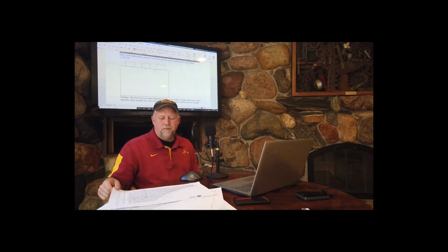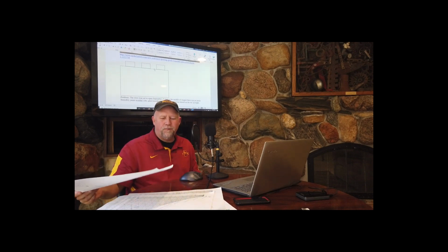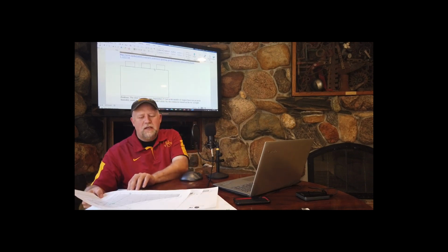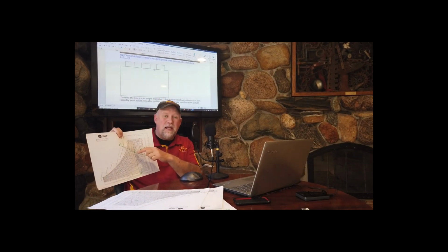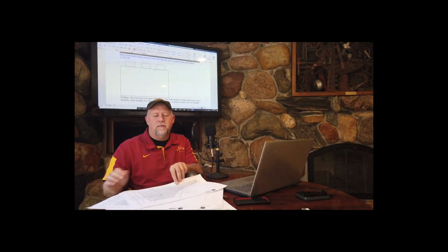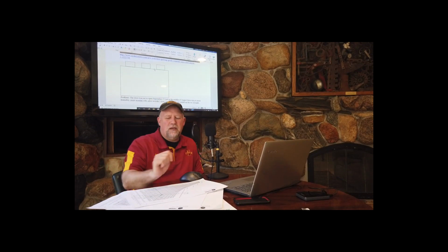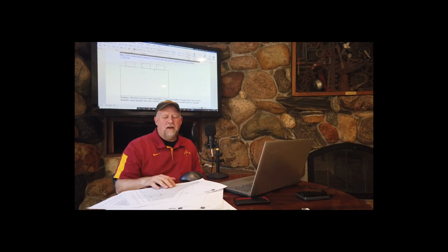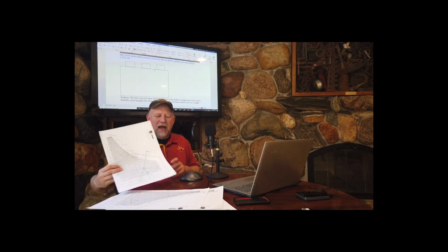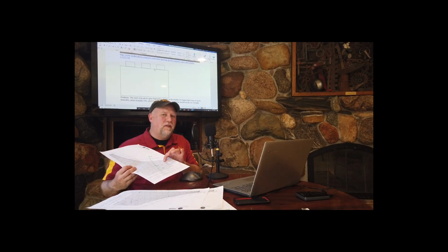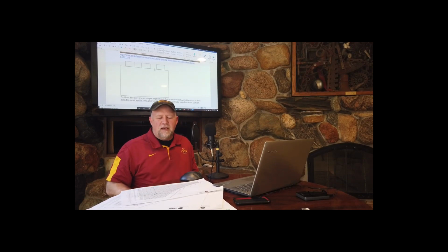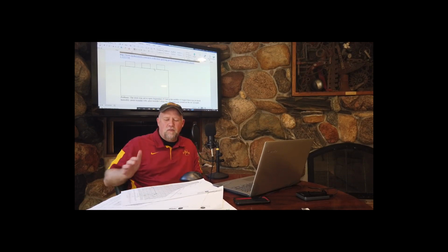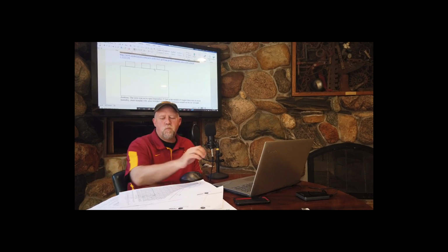Everybody grab your psych chart. All right, grab your psych chart. Go back to the one where you plotted outside air, and just start there. It was hot. It was humid. They turned on the air conditioning. Let's say that the inside conditions of that Dick's Sporting Goods when they went to turn on the air conditioner was 95 degrees, 50% relative humidity. Just remember, we just plotted that. Go ahead and plot it.